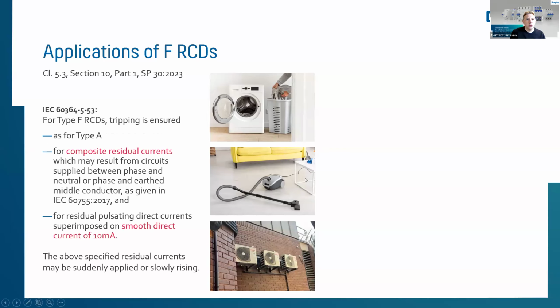So the tripping is ensured for composite residual currents, and also for direct DC currents superimposed on smooth direct currents, for a type F, up to 10 milliamp DC. That is a bit different than the type A RCDs, where it's only 6 milliamp, but for F RCDs it's a 10 milliamp threshold direct DC current.